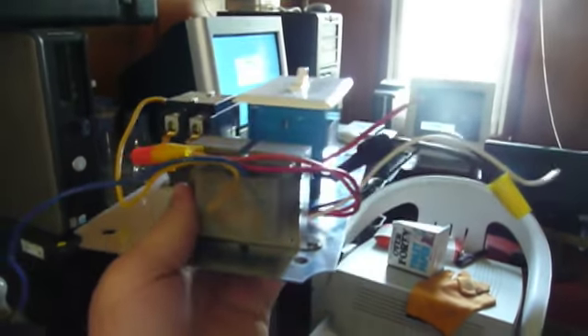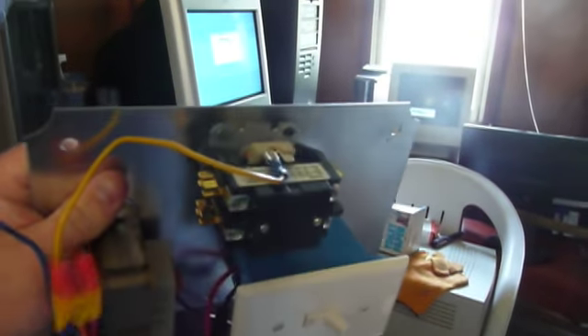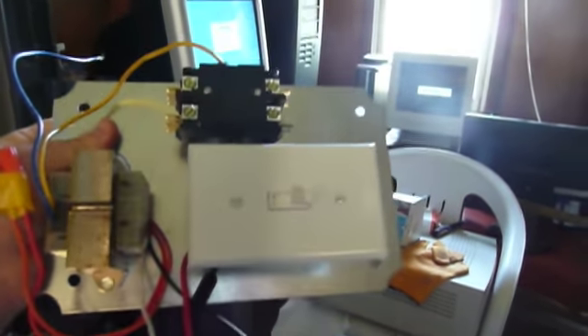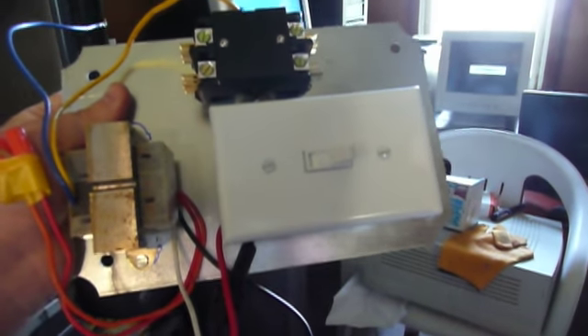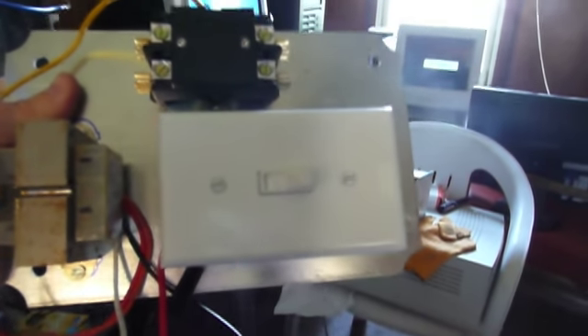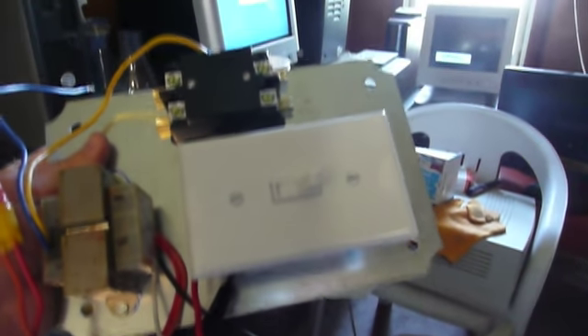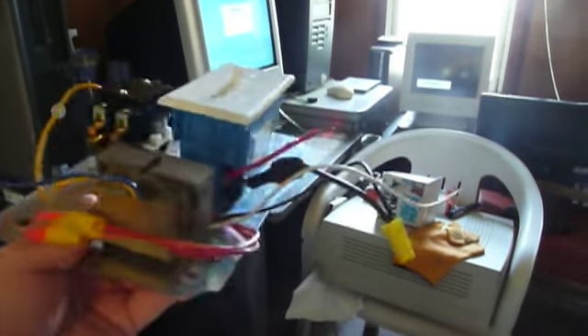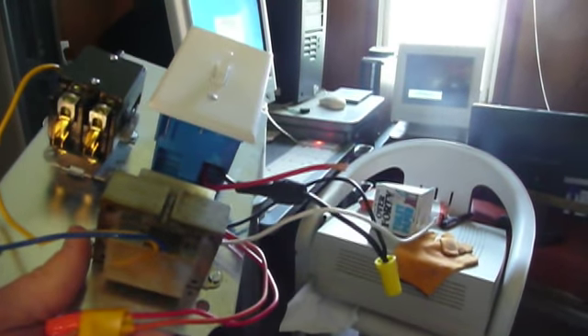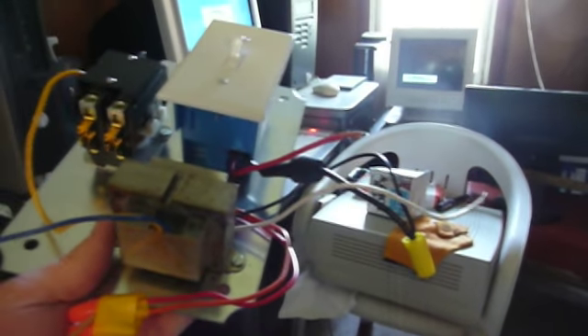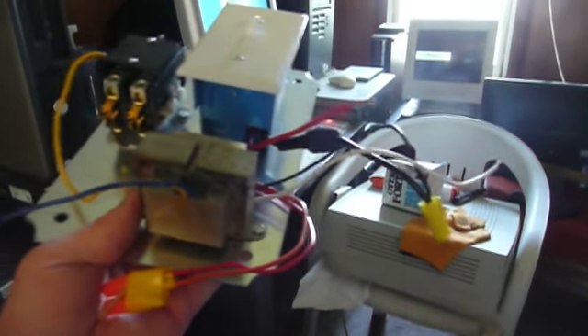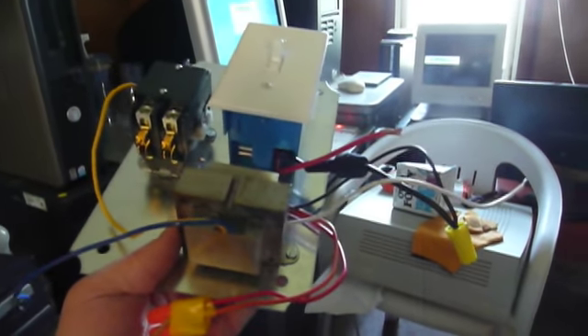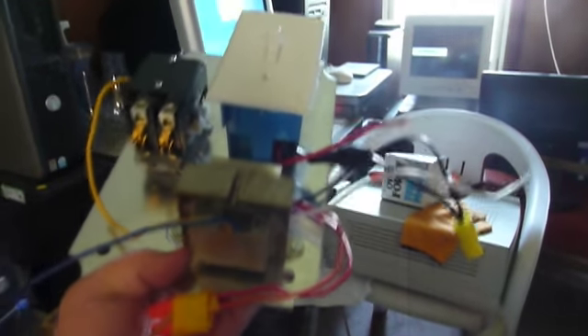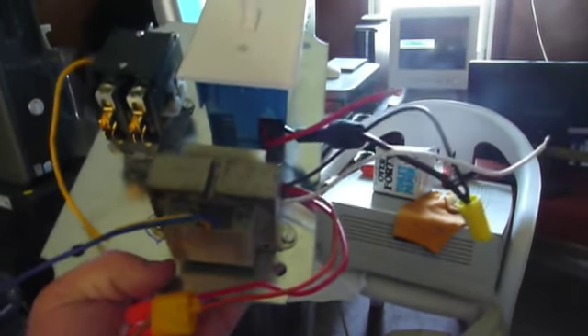We have the same old 24-volt transformer, used to provide power for the coil in the contactor. There's an on and off switch that cuts power to the transformer to assure this thing will stay off, and the thermostat can't possibly turn it on if left on by mistake. And of course there's a fuse holder in there, just like the last one, to protect the transformer in case anything goes wrong. If you have a fault in a transformer this small, a 15 or 20 amp circuit breaker isn't likely to notice until there's smoke coming out of something, but a 1 or 2 amp AGC fuse ought to blow pretty quickly if there's a serious enough problem.